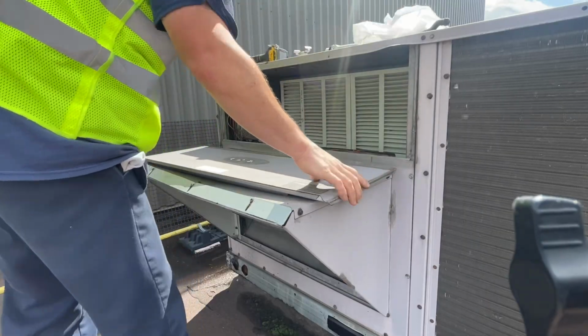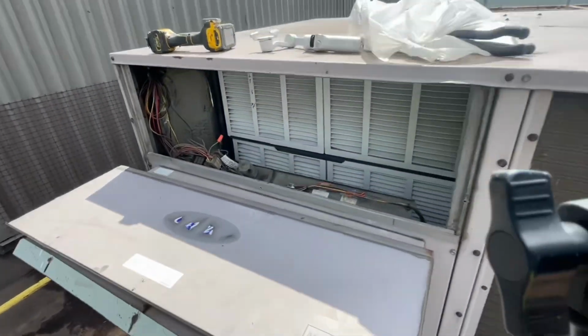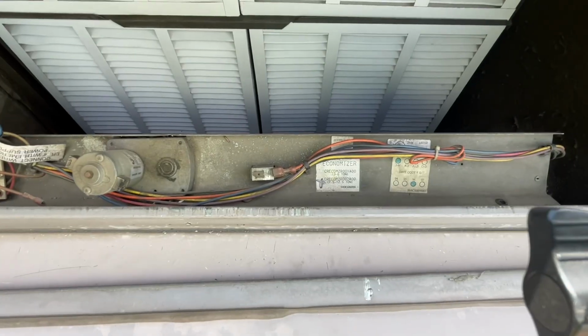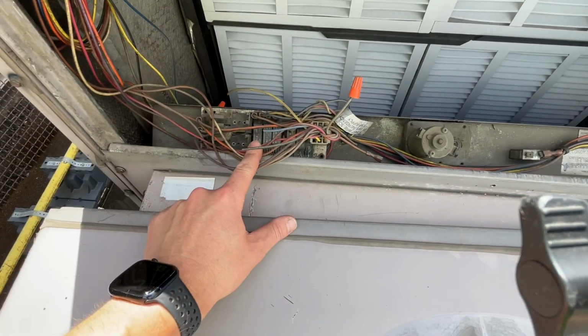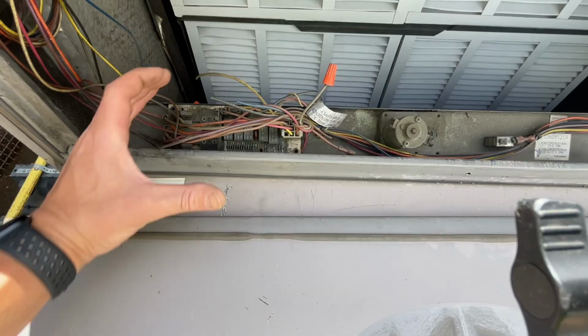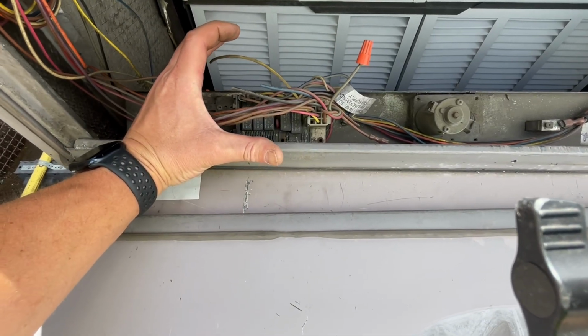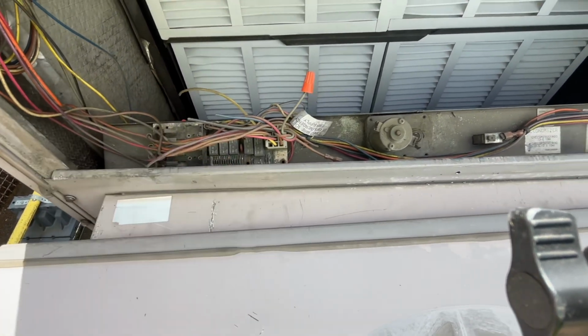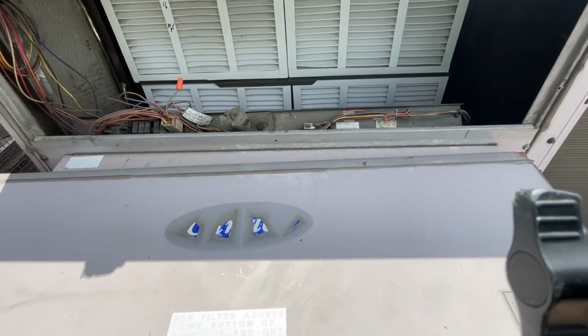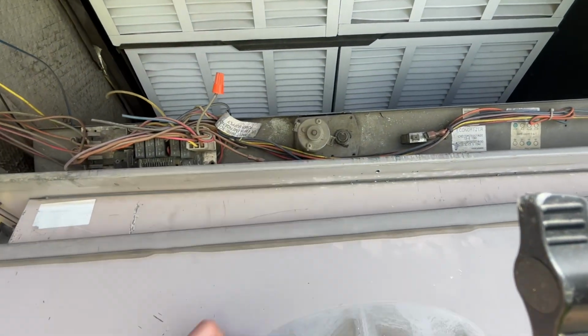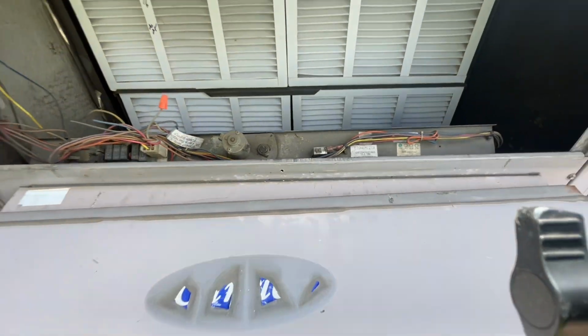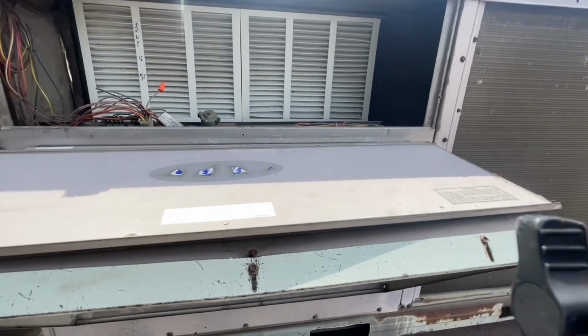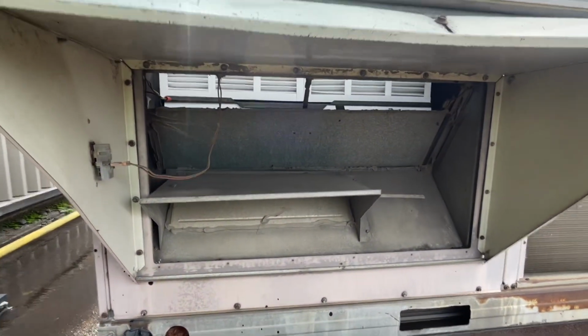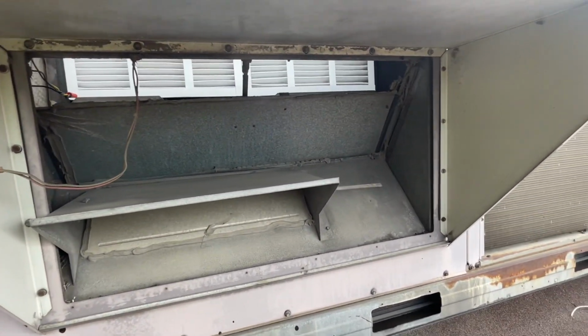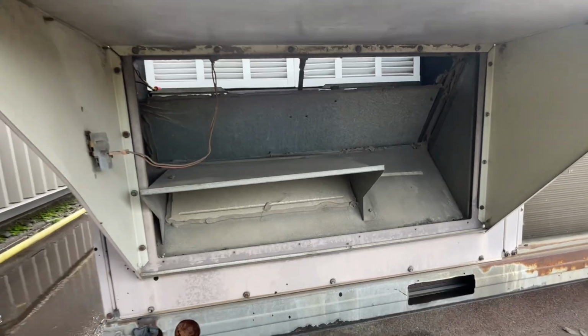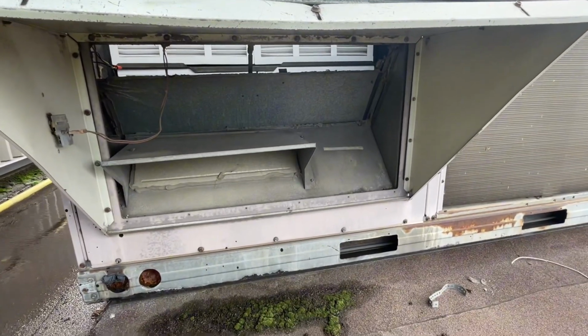Just pop that door open, and usually you can see right there, it's stamped economizer, but you'll have a board in here. The newer ones will actually have, depending on the brand, a Jade controller, so it could be digital. They all have actuators. That was here once upon a time. This unit's very, very old, so this wouldn't apply to most of the newer stuff we have, but there we go. It looks like somebody's forced this one open, I guess to get some free cooling. I don't know if it's gonna do them any good when it's 40 degrees Celsius.